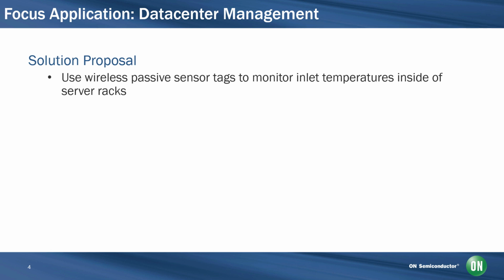To mitigate these issues, one solution is to use wireless passive sensors to monitor the air temperature inside server racks. Having a detailed heat map enables data center managers to adjust the amount of cooling in the data center based on demand to improve energy efficiency.